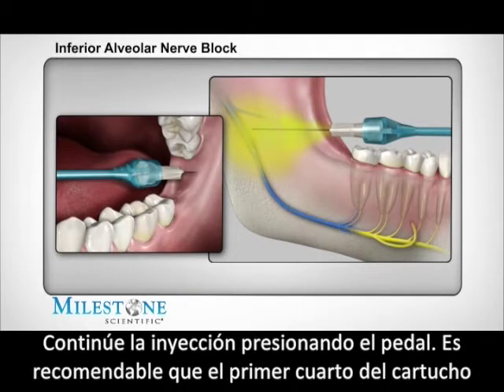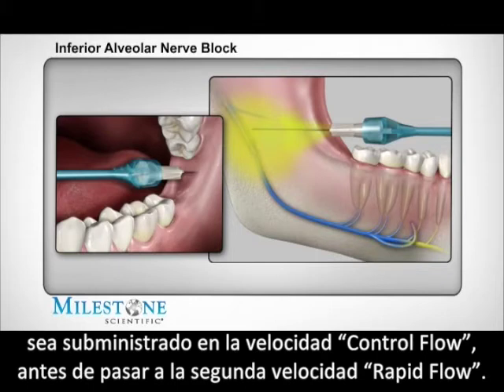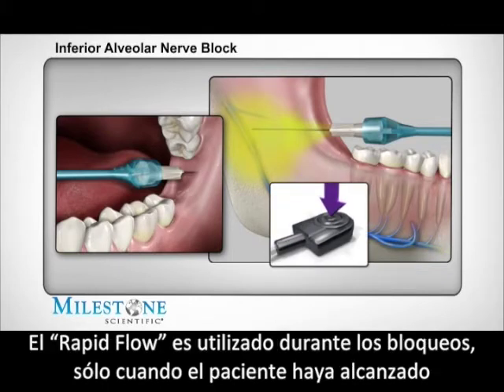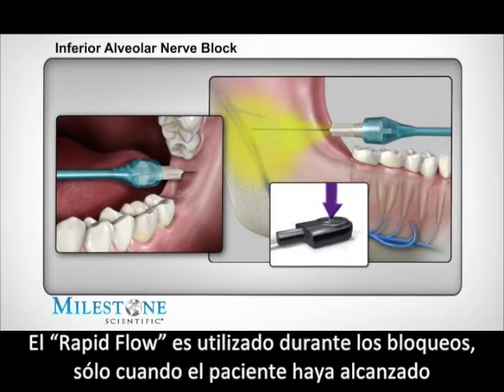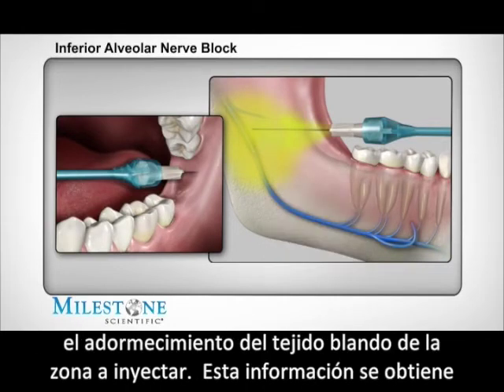Continue the injection by depressing the foot control pedal. It's recommended that the first quarter of the cartridge be dispensed using the control flow rate before transitioning to the second, faster rapid flow rate. The rapid flow rate is used during block injections only after your patient has acknowledged that they have achieved soft tissue anesthesia of the area being injected.